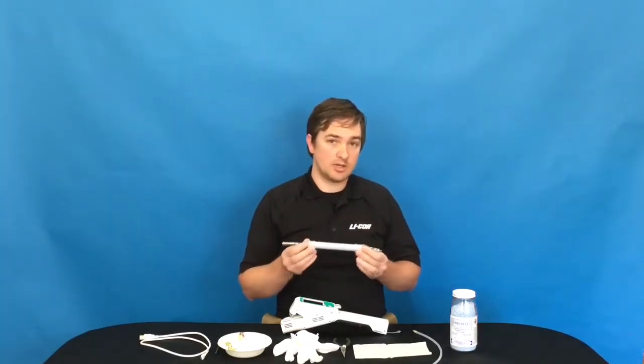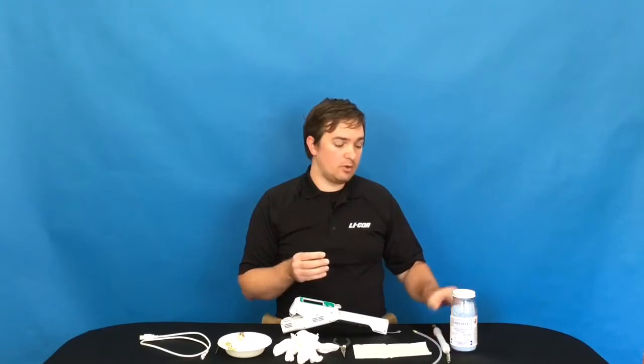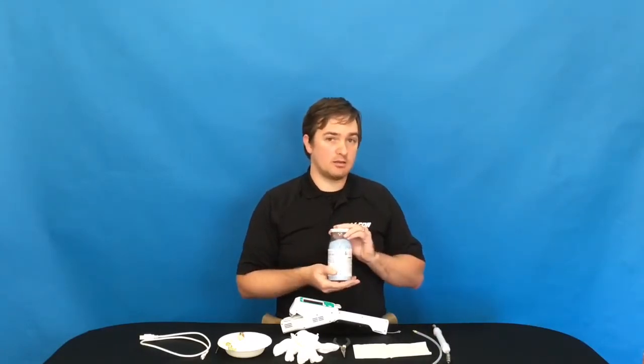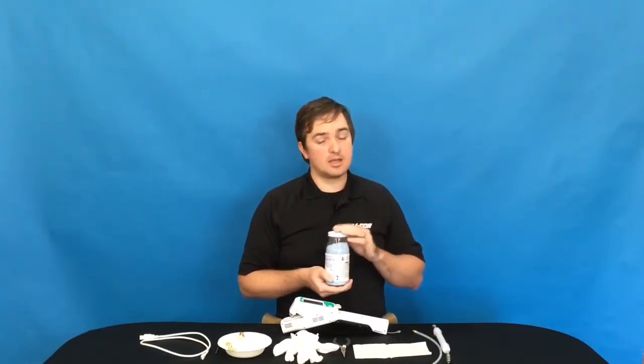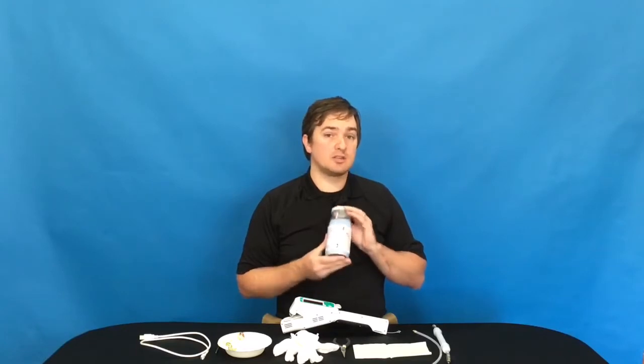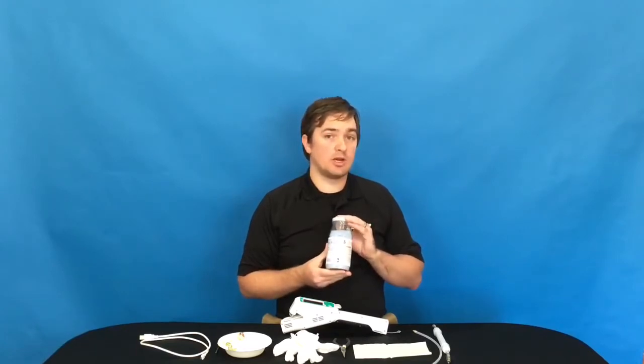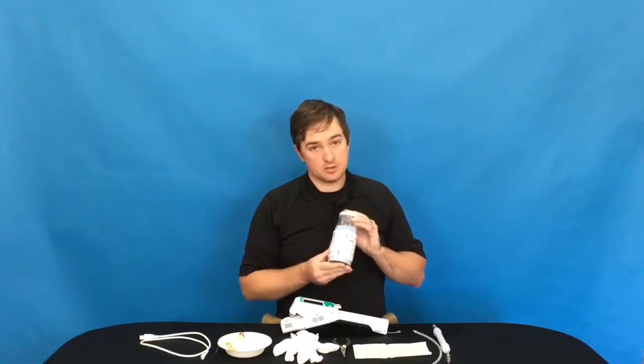Last, you'll need the zero kit that came with the instrument, and you'll want to fill that up entirely with desiccant. We recommend using Drierite. It can be indicating or non-indicating Drierite, but make sure that it's fresh. You don't want to be calibrating with exhausted chemicals. So you'll want fresh Drierite.